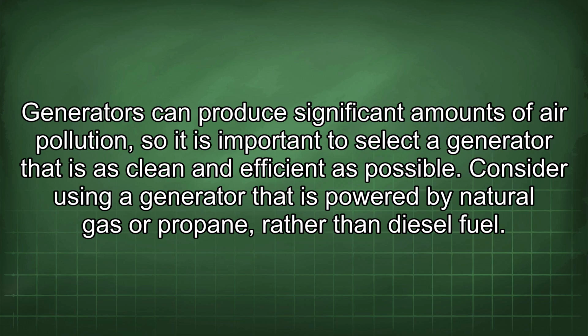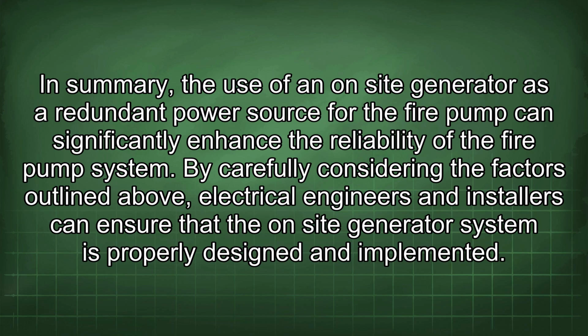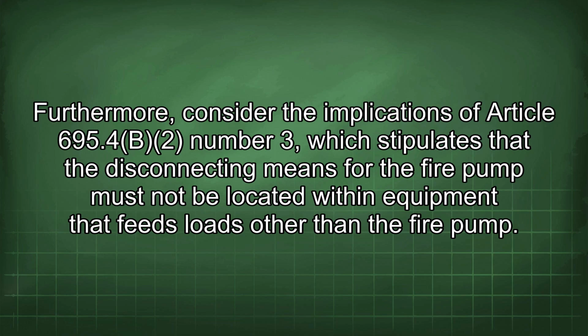Consider using a generator that is powered by natural gas or propane, rather than diesel fuel. In summary, the use of an on-site generator as a redundant power source for the fire pump can significantly enhance the reliability of the fire pump system. By carefully considering the factors outlined above, electrical engineers and installers can ensure that the on-site generator system is properly designed and implemented.